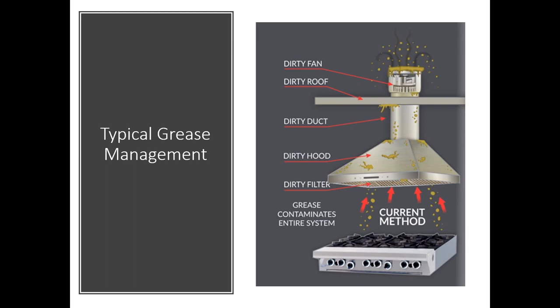Grease deposits also accumulate anywhere there is a change in airflow speed or direction. Beginning with the transition from the hood to the ductwork, each bend in the ductwork, or even long runs in the ductwork where air speed flow changes. Then, as air is pulled through the fan blades, this is another key point of accumulation before the final particles are exhausted into the air above the building, settling back onto the roof and into your AC cooling coils.